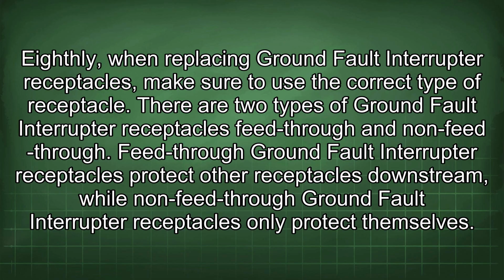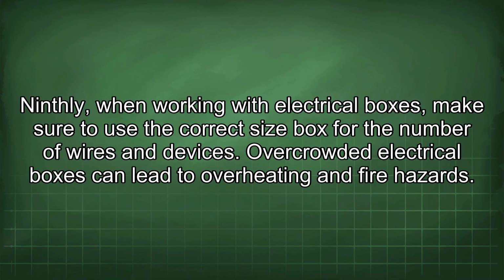Eighthly, when replacing ground fault interrupter receptacles, make sure to use the correct type of receptacle. There are two types of ground fault interrupter receptacles: feed-through and non-feed-through. Feed-through ground fault interrupter receptacles protect other receptacles downstream, while non-feed-through ground fault interrupter receptacles only protect themselves. Ninthly, when working with electrical boxes, make sure to use the correct size box for the number of wires and devices. Overcrowded electrical boxes can lead to overheating and fire hazards.